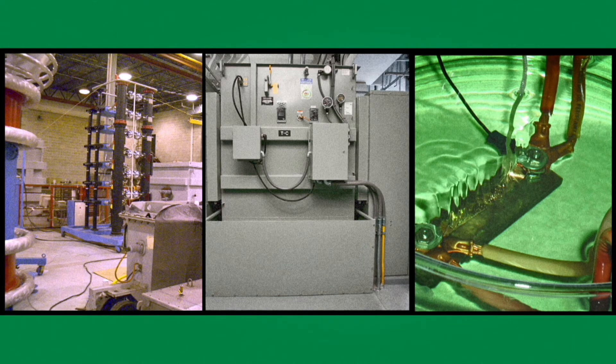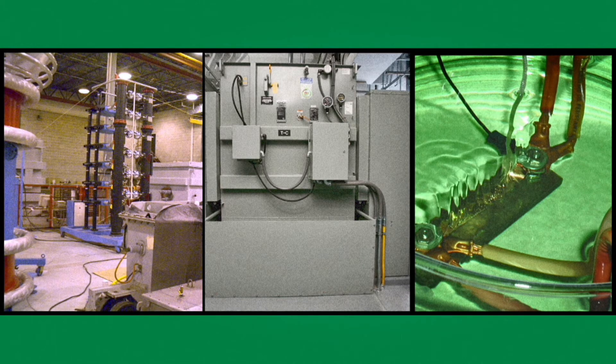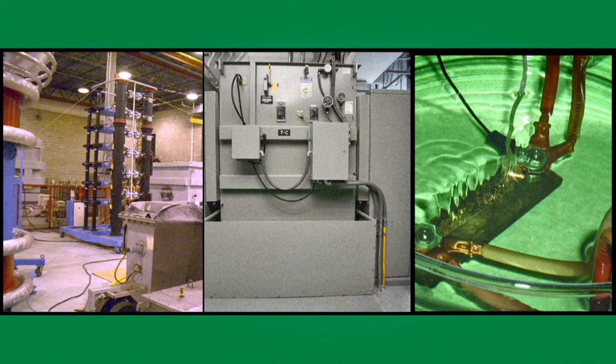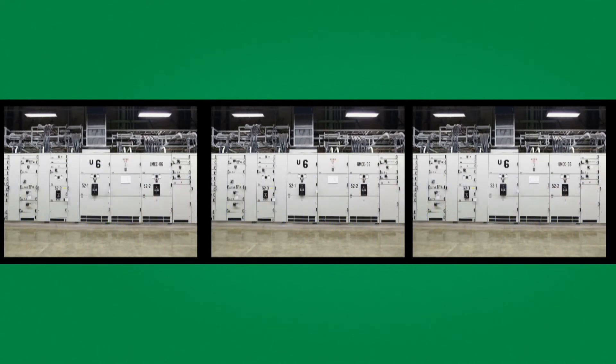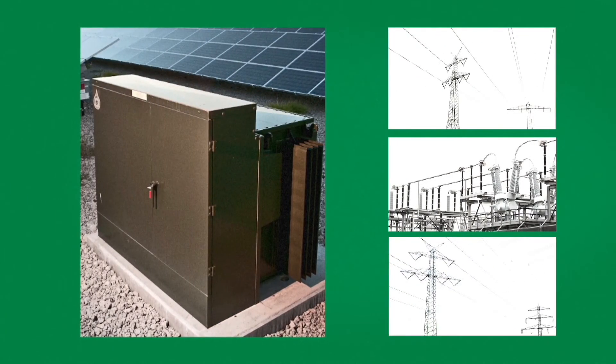Where we bring value is where you can design not only transformers but systems like substations using the product qualities of a natural ester. With new high-temperature standards, you can raise the operating temperature, making the transformer smaller and more efficient, using less materials, getting close to or even lower than the cost of a mineral transformer.